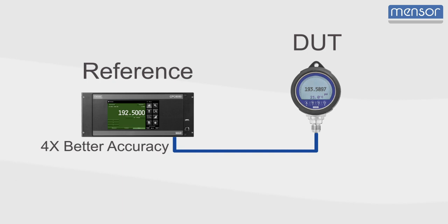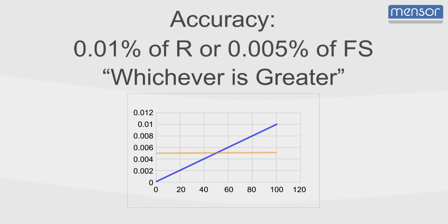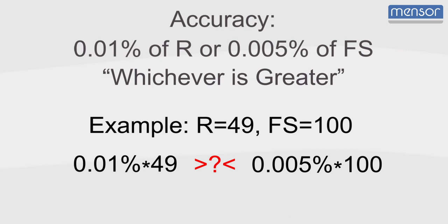In the calibration industry, it is common to indicate accuracy as a combination of percent of reading and percent of full scale, whichever is greater. The phrase whichever is greater implies you have to do a calculation to determine if the percent of reading or percent of full scale applies at your measuring point.